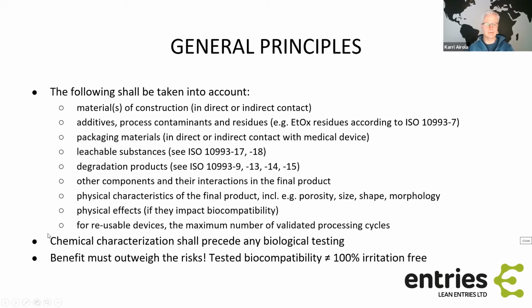And this again mentions that chemical characterization should always precede any biological testing, and eventually the benefit should outweigh the risks. So even though you have tested successfully that your device is biocompatible, it could very well be that it's not 100% irritation free. There are always some unexpected reactions with some sensitive patients. So you might get a sensitization reaction, even though your device was tested to be non-sensitizing in the biocompatibility testing. And this is something to be followed in the post-market phase of your product.